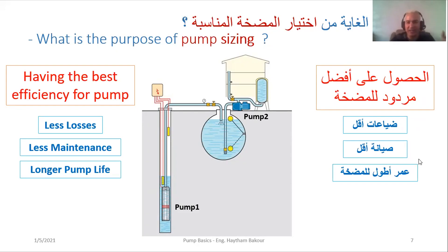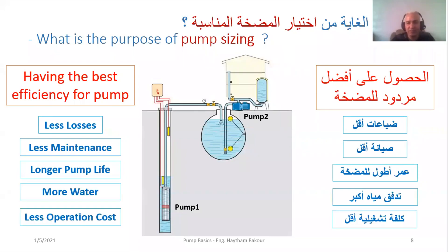A pump can be available for 25 to 30 years. In Syria, we had pumps in irrigation areas in wells working for 20 to even 30 years without maintenance. Within wells, the maintenance procedures are really hard to carry out. When I choose the pump with less efficiency, this pump wouldn't last over 10 years. With good size, I have more water flow and less operational cost — so with good choice: less maintenance, less losses, more water, longer pump life, and less operational cost.